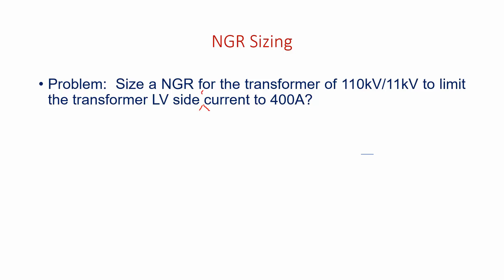We have to reduce transformer LV side single line to ground fault current to 400 amps. This is my objective. You can observe the transformer secondary line voltage is 11 kV.